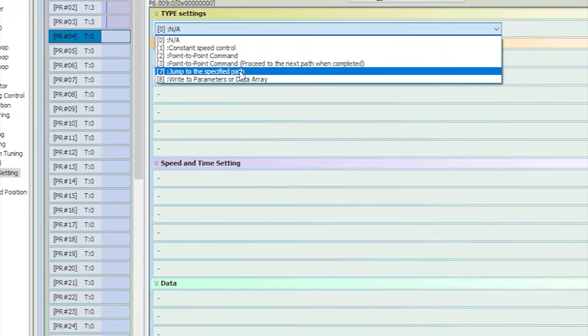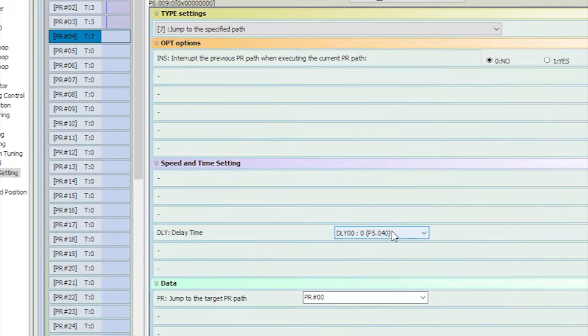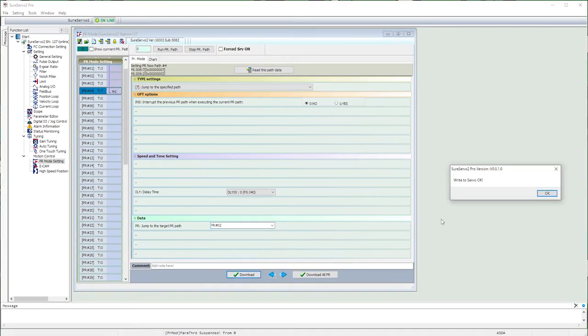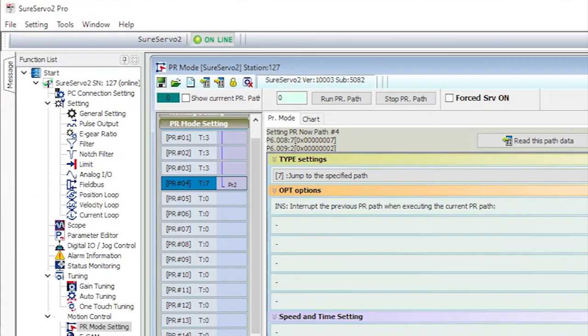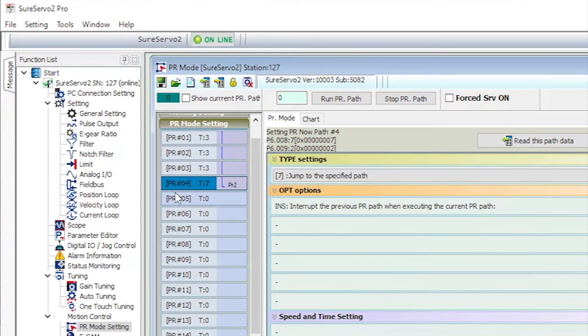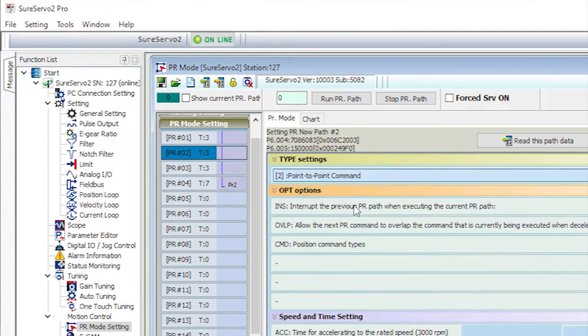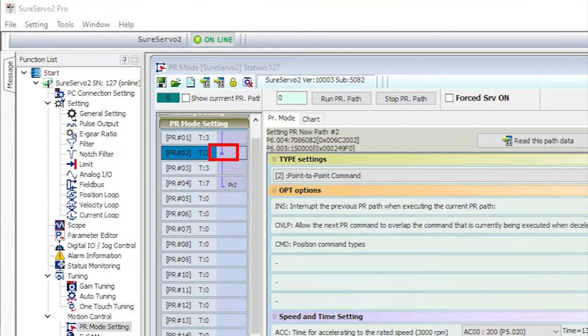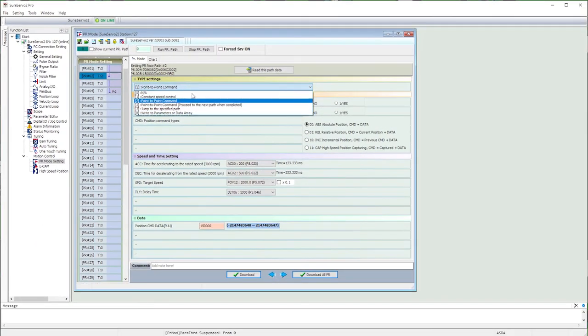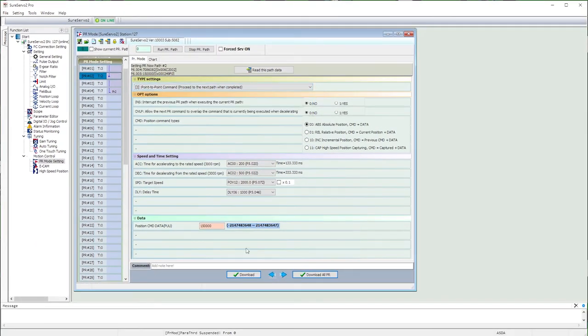And write that one out to the drive. Look at this. The software draws a little diagram of how things are going to proceed with this little blue line. The path will start at step 1 and when it hits step 4 it will jump to step 2. If I change path 2 to a simple point-to-point with no auto-advance, the blue line says to stop after this step. And I'll change that back and write it out to the drive.